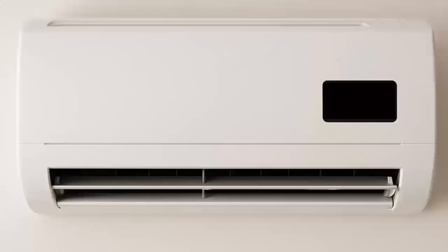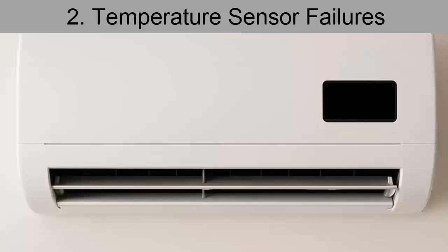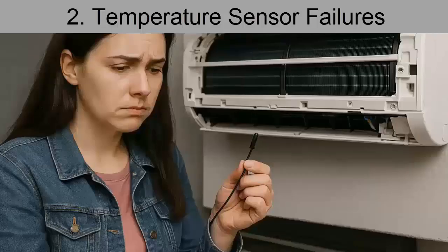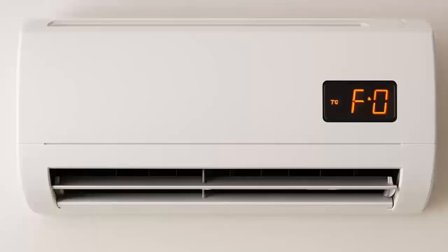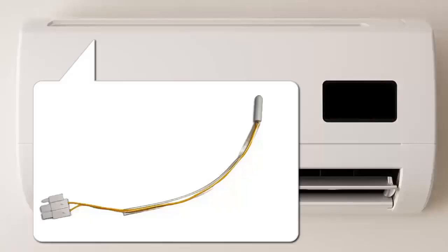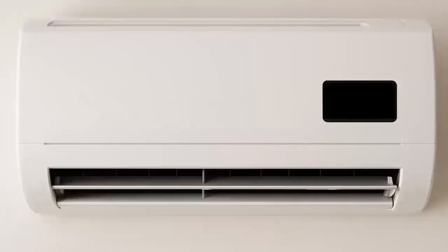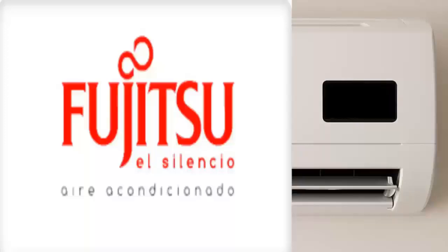Second category: temperature sensor failure on the indoor unit. The air conditioner can't properly measure room or coil temperature, or it detects a short circuit or an open circuit.